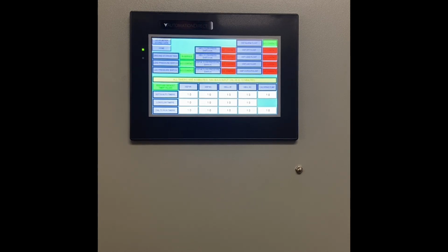Now, most of the time when PLCs are programmed, they are programmed for a specific contact type, whether it be normally open or normally closed. As somebody who has spent the last 2 decades in the field, I know that sometimes you have a normally open float and what you really need is a normally closed, and there's not a good way to make that work. Well, I made it simple on programming this one.